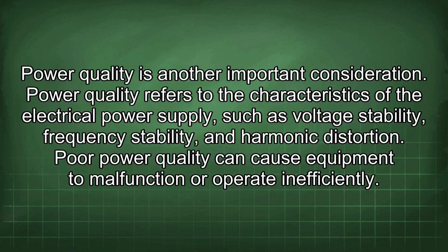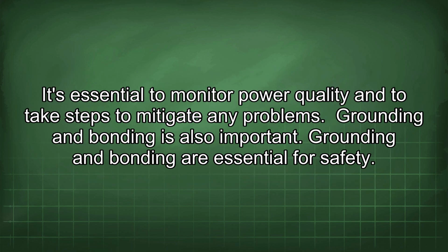Power quality is another important consideration. Power quality refers to the characteristics of the electrical power supply, such as voltage stability, frequency stability, and harmonic distortion. Poor power quality can cause equipment to malfunction or operate inefficiently. It's essential to monitor power quality and to take steps to mitigate any problems.